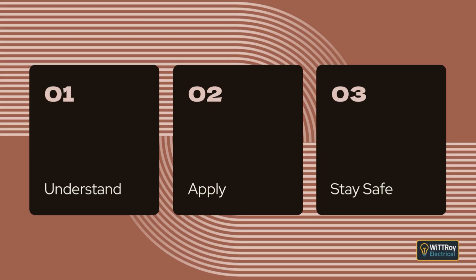Clause 1.5.12 Protection against the spread of fire. This clause focuses on fire safety. The electrical installation must not start a fire or make an existing fire spread or become worse. Equipment must be selected and installed so that it does not block escape routes with flames, smoke, or hot gases, does not add to a fire or help it spread, does not become so hot that it ignites nearby materials, and does not interfere with people trying to escape. Other parts of the standard provide more detail, including requirements for switchboard locations and fire spread control. The short message is that electrical equipment must never worsen a fire or restrict evacuation.